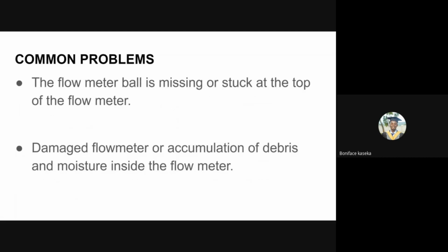So sometimes we might have a flow meter ball that is missing or stuck at the top of the flow meter. In terms of a missing flow meter ball, it can happen that the oxygen flow splitter fell down, or there was an accident of some sort, and the flow meter is cracked. So normally you would lose that ball, and if you do not have that ball, then there's no way you can tell whether you are administering the correct amount of oxygen to a patient, and that is not ideal, and that is fatal. Sometimes the flow meter ball is stuck at the top.